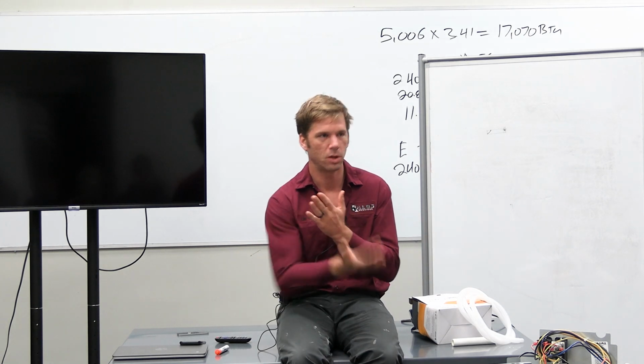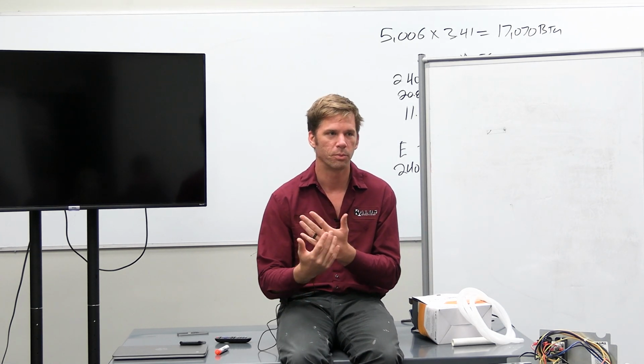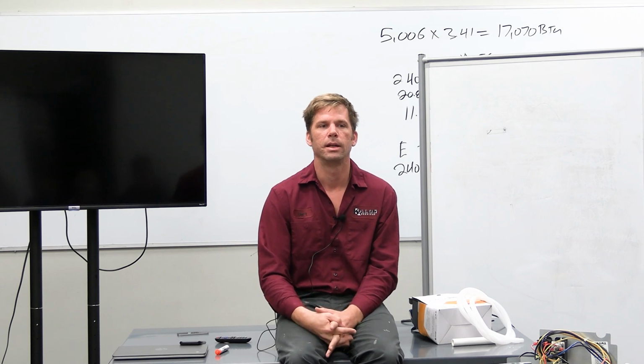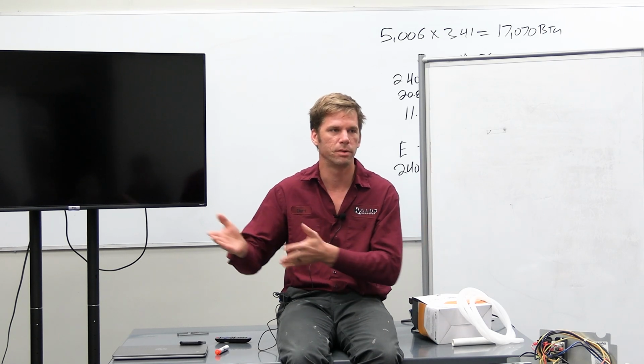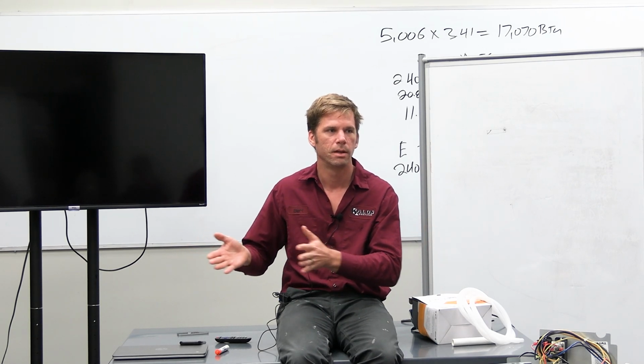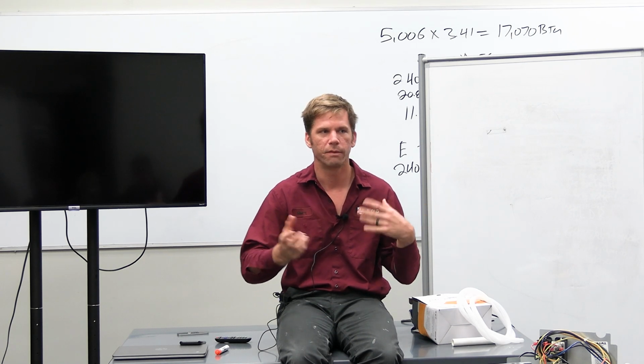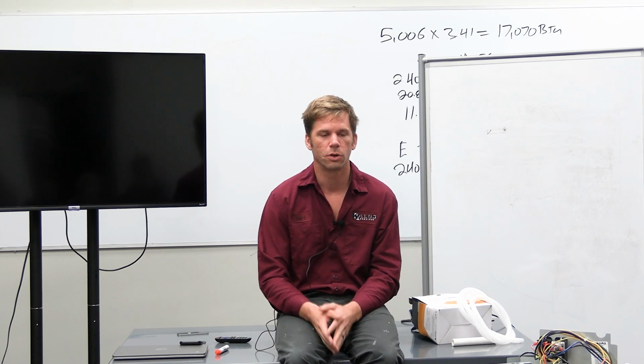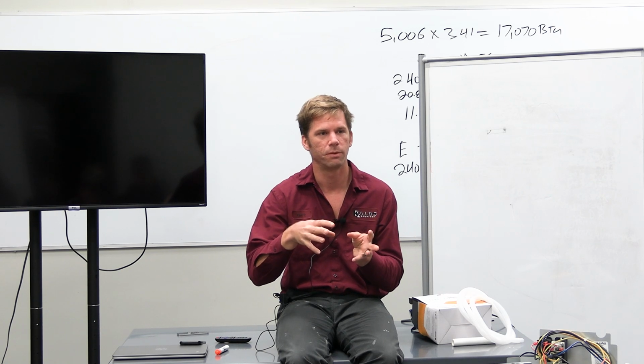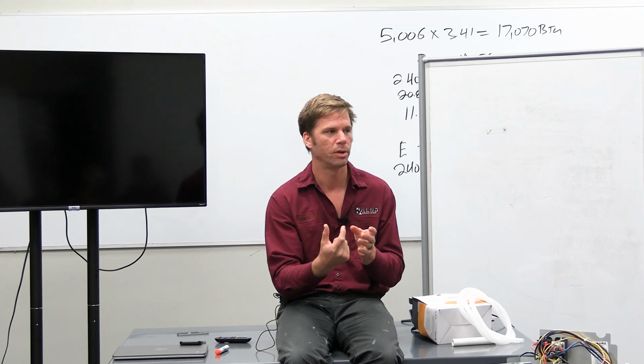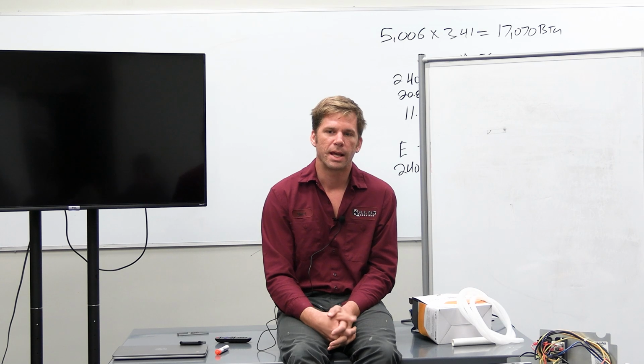So if that valve has been opening and closing a lot, it can break, it can crack. And so you show up and the pool heater's making a weird sort of hissing sound. No matter what you do, even though water flow seems fine in the pool area, the heater's overheating and shutting off, it's shaking. You actually have to open up the heat exchanger manifold, find that valve, pull it out, see if it's cracked.